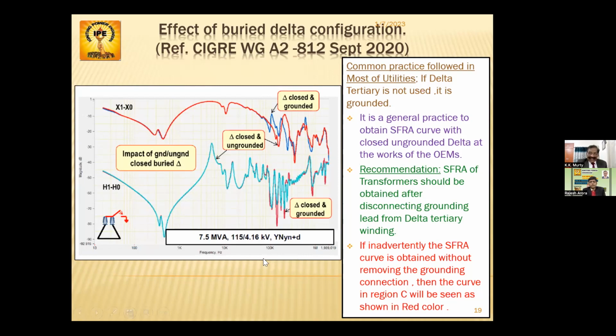it is grounded. It is a general practice to obtain the SFRA curve with the closed ungrounded delta in the works of the OEM. When you go to the OEM for FAT, that is factory acceptance test, you will find that they will take this SFRA curve with closed delta ungrounded. So this is the closed delta ungrounded curve. So in practice also, when you are testing the transformer with closed delta, you have to remove the earthing lead from the delta bushing, that is the U3 bushing.